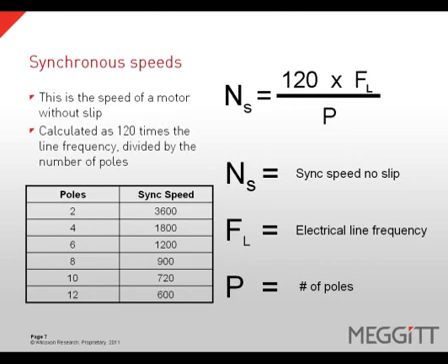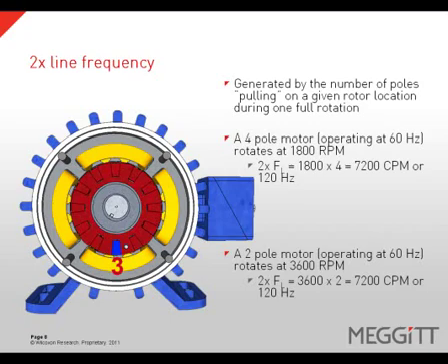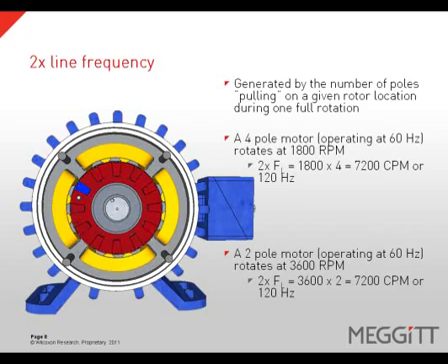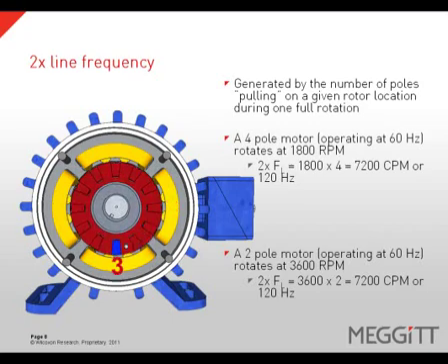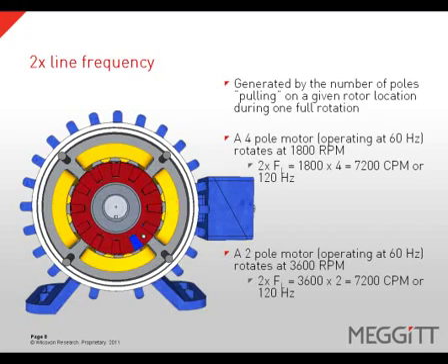For a two-pole motor, the synchronous speed would be 3,600 RPM. Two-times line frequency is generated by the number of poles pulling on a given rotor location during one full rotation. A four-pole motor operating at 60 hertz rotates at 1,800 RPM. To determine two-times line frequency, we take 1,800 times four poles and get 7,200 CPM or 120 hertz. A two-pole motor operating at 60 hertz rotates at 3,600 RPM. Two-times line frequency can be calculated by taking 3,600 RPM times two poles to get 7,200 CPM or 120 hertz.